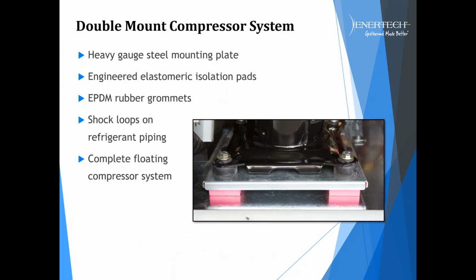Our double mount compressor system. This has also been integrated into all of our products at Enertech over the last few years. And of course, this is also in the ZSZT model. And this is designed, highly engineered, again, based on the weight of the compressor. So the Getzner pads, or the pink pads that you see there, they actually are different densities based on the weight of the compressor. So you've got a heavy gauge steel plate, a set of rubber grommets, and then you've got the Getzner pads in there that allow that compressor to be 100% floating and just absolutely dead quiet. And this next year we will offer and be publishing sound data.